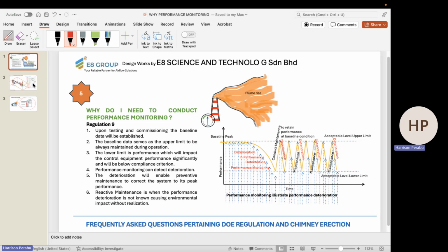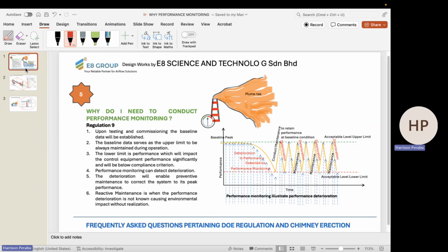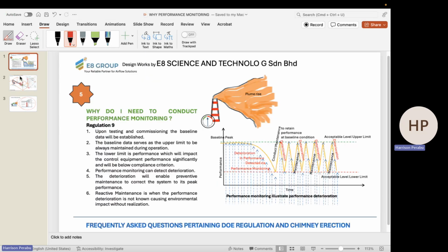You see, you observe. Now, as for DOE, you are supposed to do the differential pressure. As for DOSH, LEV assessment wise, once a month, you must take the bare minimum performance of your hood. So if you are taking an anemometer reading, and if you are taking this, you must be able to correlate. When the DP goes up, anemometer reading goes down. So how low does it go down? If it goes down up to 80, then it's about time for you to service. So you trigger that. You take charge of the control. So that's exactly how it works. So you can start out with a rule of thumb, but eventually you can control by measuring the lowest point of capture velocity.